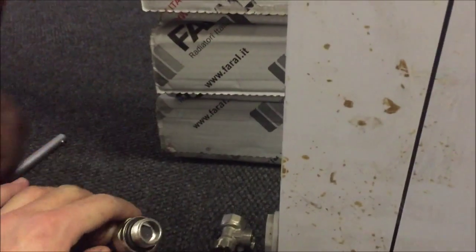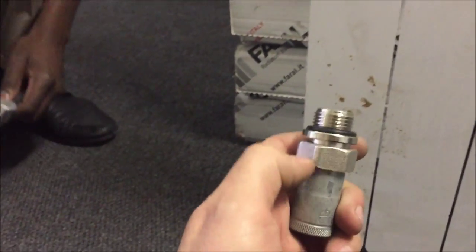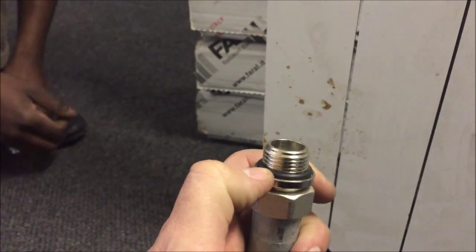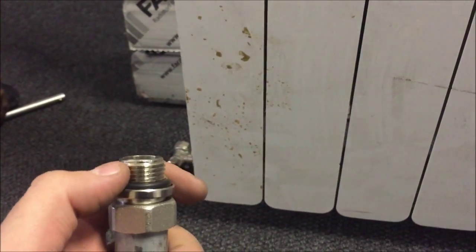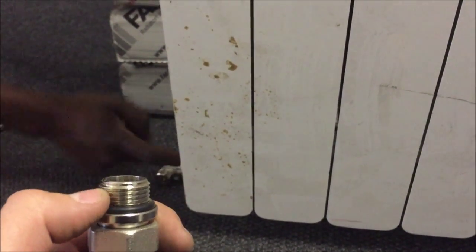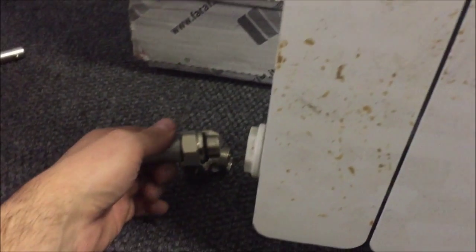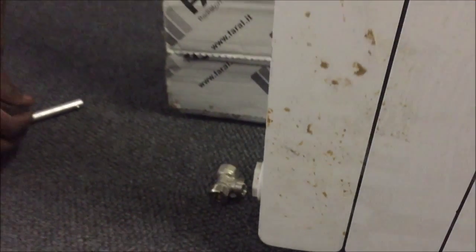Normally the reason why it's leaking is because this rubber seal is not sealing properly here. It's normally due to the radiator, so what I do is I apply hemp on this thread, re-apply it, and then re-tighten everything.